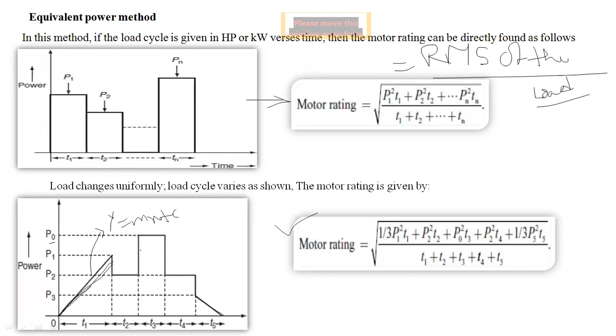Here the variation is the slant, the inclination, the slope of your load. This can be considered as a slope, y equals mx plus c. We can easily understand this. So again, the load has been changed uniformly. For each and every load on your time basis, the power is generated, thus P0, P1, P2, P3. So again, here we have the slope variation. Just check the equation for the motor rating from this load cycle. Earlier I said the motor rating always depends upon the RMS of the load. Therefore, square root of 1 by 3 of P1 square T1 plus P2 square T2 plus P0 square T3 plus, and so on, because whatever values you have taken are mentioned as P0, P1, P2. So the duration of T2, please hold on, just power off.